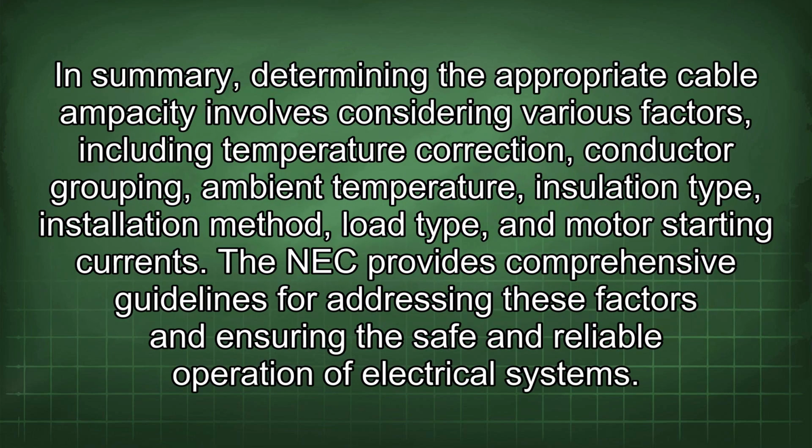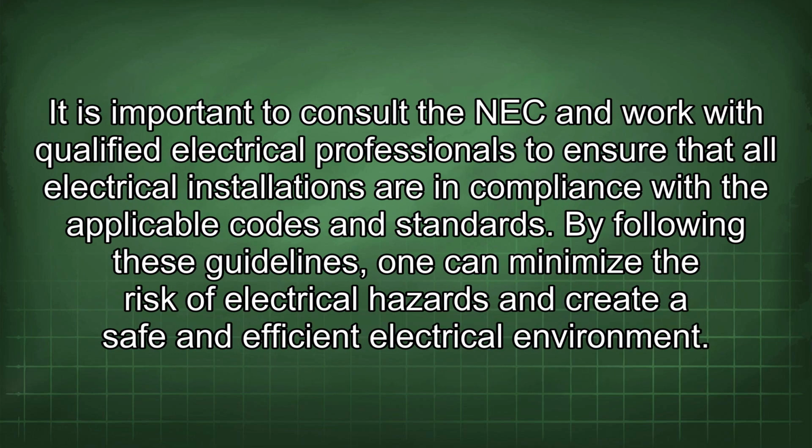In summary, determining the appropriate cable ampacity involves considering various factors, including temperature correction, conductor grouping, ambient temperature, insulation type, installation method, load type, and motor starting currents. The NEC provides comprehensive guidelines for addressing these factors and ensuring the safe and reliable operation of electrical systems. It is important to consult the NEC and work with qualified electrical professionals to ensure that all electrical installations are in compliance with the applicable codes and standards. By following these guidelines, one can minimize the risk of electrical hazards and create a safe and efficient electrical environment.